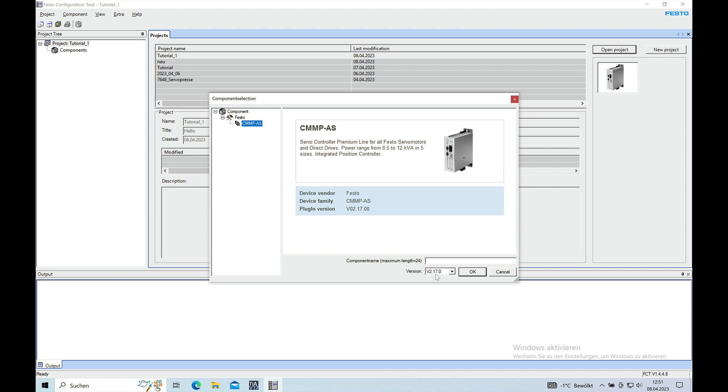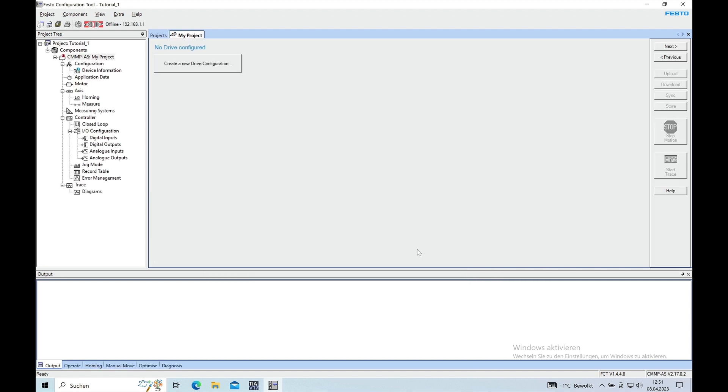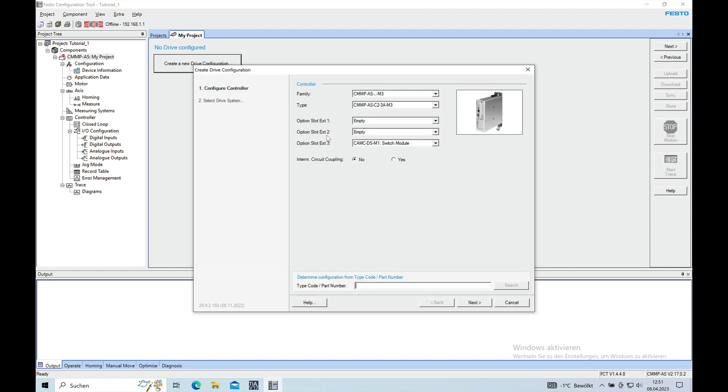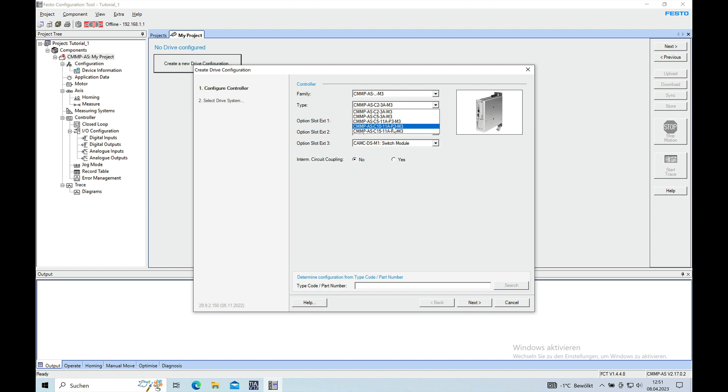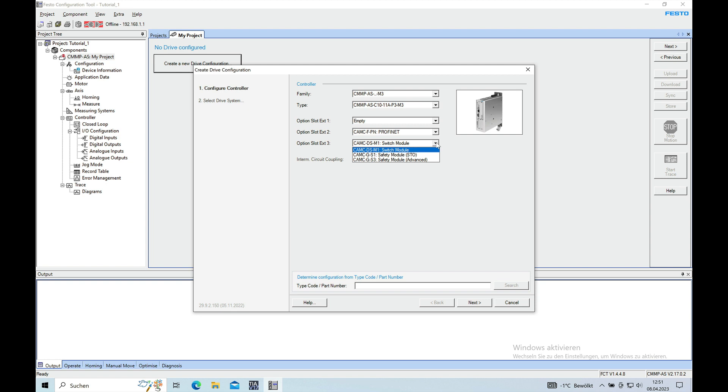You need to choose your CMMP AS and give this a name again, my project for example. Go ahead, push OK, and then at first you need to create a new drive configuration which is according to your hardware components. I have a CMMP AS M3 with the 10 amp, 11 amp controller with Profinet. Nothing in the extension slot one, and extension slot two includes the Profinet board and I have a safety module STO.